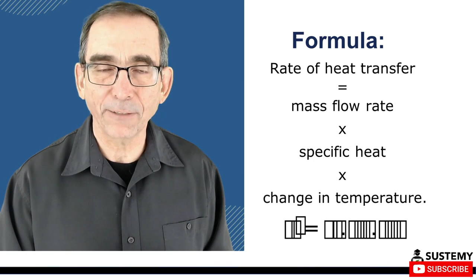Here we have the water flow rate of 7.2 meters cubed per hour, a water density of 1,000 kilograms per cubic meter, and there's 3,600 seconds in an hour. Combining those numbers, we get a water mass flow rate of 2 kilograms per second. The temperature in is 12 degrees Celsius. The temperature out is 5 degrees Celsius. That gives a delta T of 7 degrees Celsius or 7 degrees Kelvin.